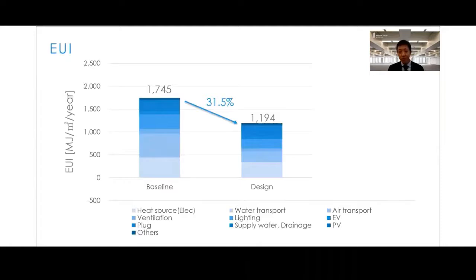Based on the local simulation method, the EUI for the whole building is estimated at approximately 1,200 megajoules per square meter per year on a source basis. The baseline model was approximately 1,800. Thus, this project is expected to yield energy savings of 30% or more. The actual measured energy consumption for the first year after completion was 1,400.